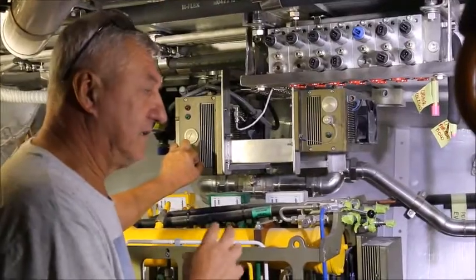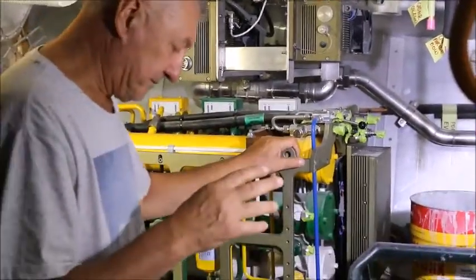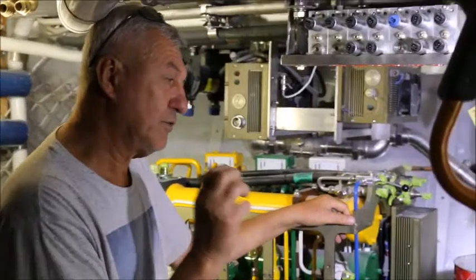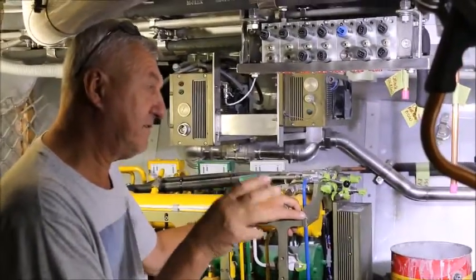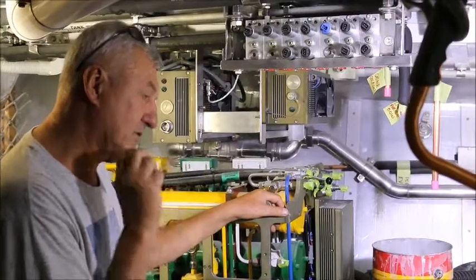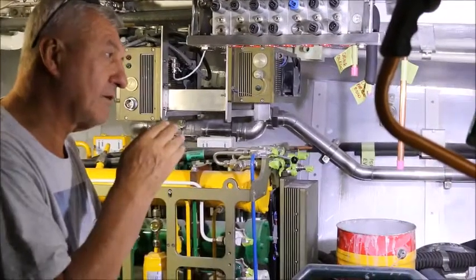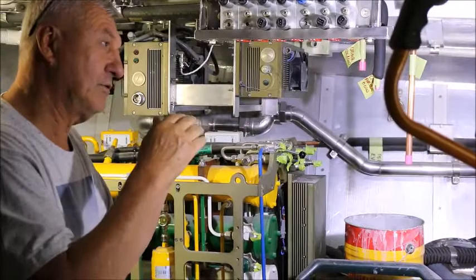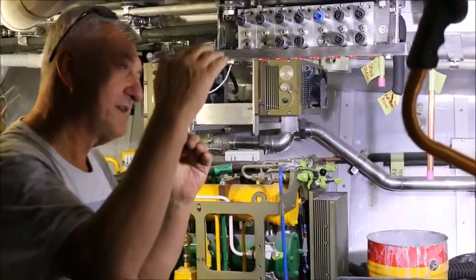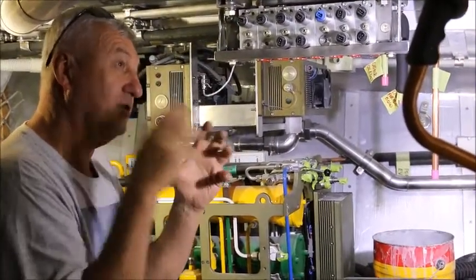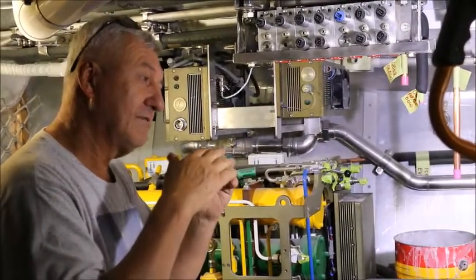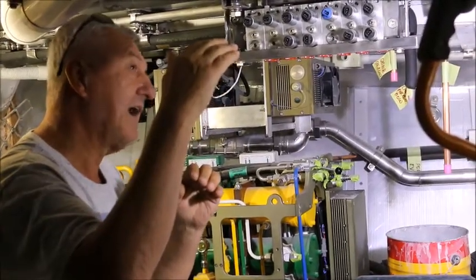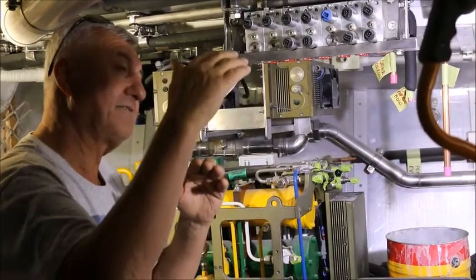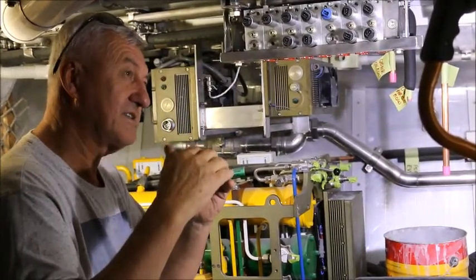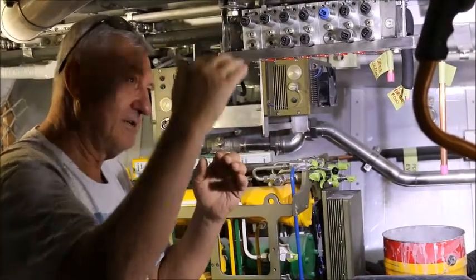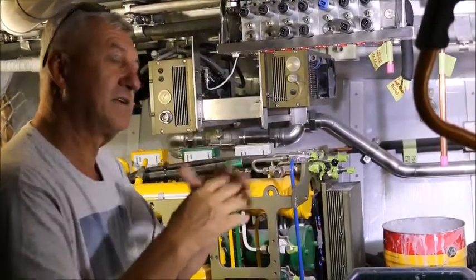Doesn't matter. What I found out from experience is because we have a soft start, we took a 15 amp circuit breaker on the marina and squeeze out 25 amps because it grows very, very slowly. By the time you freeze the freezers, the demand drops and the current drops, so the circuit breaker would get hot and pop out. But when you're running it with a soft start, the circuit breaker will tolerate higher current for maybe half an hour. After that, as you compress the gas, there's less pressure, so the power goes below 15 amps, then below 10, and you're fine. And then you're air conditioning.